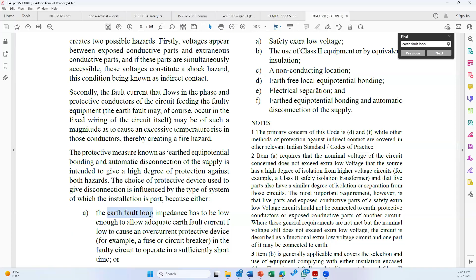To reduce touch and step voltage, an earth pit, whether a vertical pipe or a plate, is not going to help you. You need to have voltage grading. As I said, these standards are based on some information which is too old. Now we are upgrading these standards, and a lot of improvements are required. I would like to tell all the participants that the idea of thinking earth pit saves people is wrong, please remove it from your mind. Fault protection is achieved by protective equipotential bonding and automatic disconnection of supply, so both need to be there.